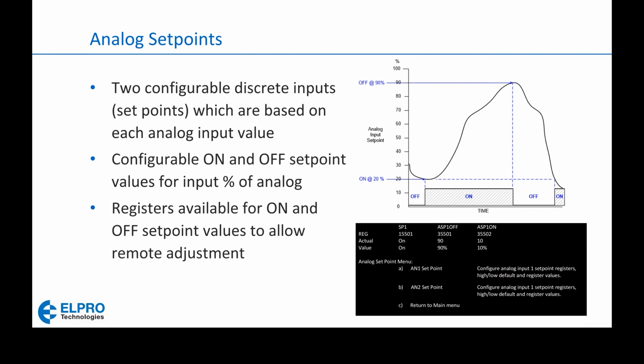For the analog set points, these are triggered off the analog input, and they're designed to fill a tank. So, for example, when the analog value drops down to a low point, maybe 3 or 4 or 5 milliamps, we would want that output to turn on.